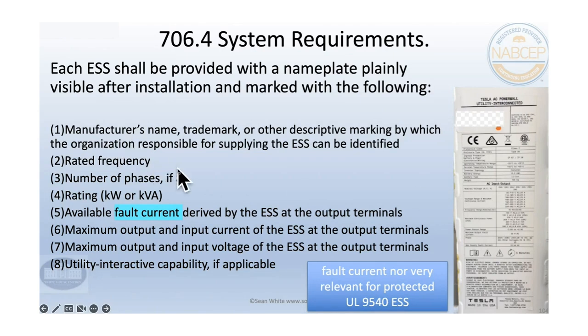frequency, and all that. Fault current is kind of silly when you're coming out of an inverter or a DC to DC converter, because the fault current is going to be very close to the operating current. They put that in there, I think, by mistake, because they are looking at our old lead acid batteries, where if you cross positive and negative, you can have an explosive amount of fault current.